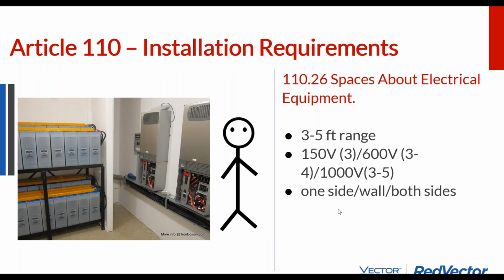There's a rule for whatever is behind you as well. And I'm not for memorizing all the numbers and tables, although they do show up on electrical exams. So what I think about is, the range is 3 to 5 feet, and there's less of an allowance for lower voltage systems. Once you get into higher voltage systems, you're up at the maximum allowance. And then on top of that, it depends on what's behind you.